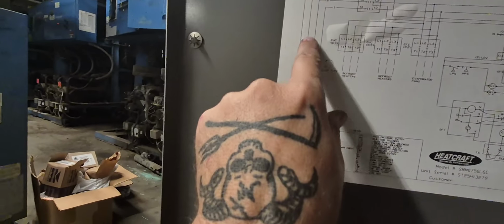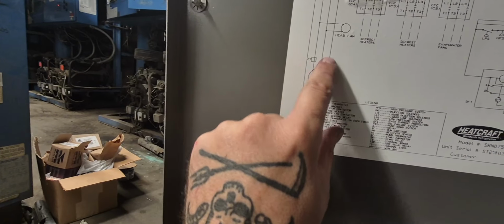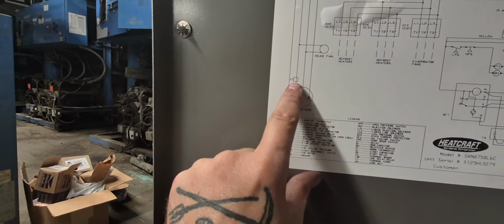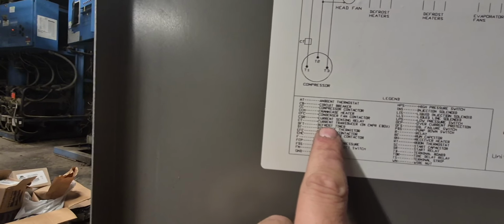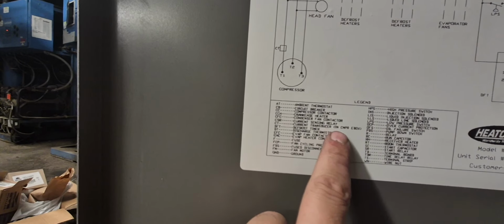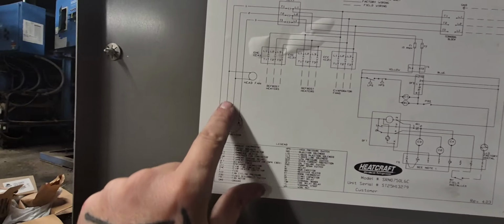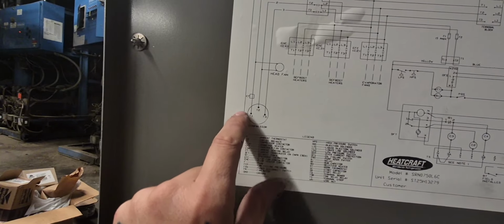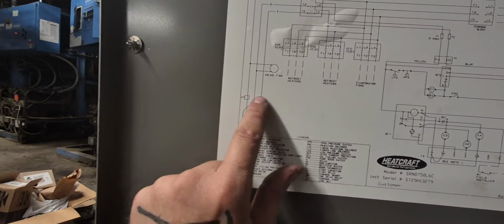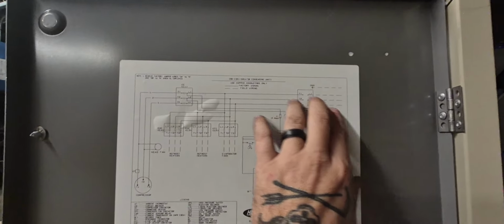But keep going, so we have our head fan right there. You come down, you can see we have a CT. So what's a CT? Let's look at our legend. CT, current transducer in compressor E-box. So we know we've got a CT that's supposed to be on L1, and then you can see it just connects to our compressor. And that's our entire high voltage side.